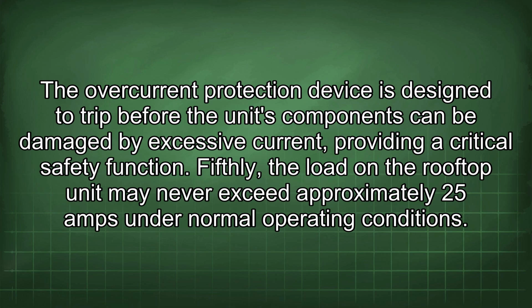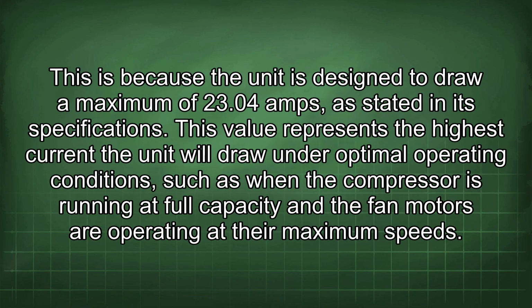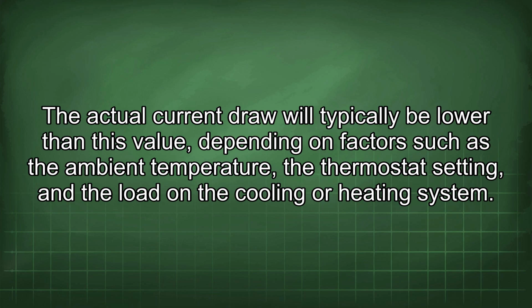critical safety function. Fifthly, the load on the rooftop unit may never exceed approximately 25 amps under normal operating conditions. This is because the unit is designed to draw a maximum of 23.04 amps as stated in its specifications. This value represents the highest current the unit will draw under optimal operating conditions, such as when the compressor is running at full capacity and the fan motors are operating at their maximum speeds. The actual current draw will typically be lower than this value, depending on factors such as the ambient temperature, the thermostat setting, and the load on the cooling or heating system.